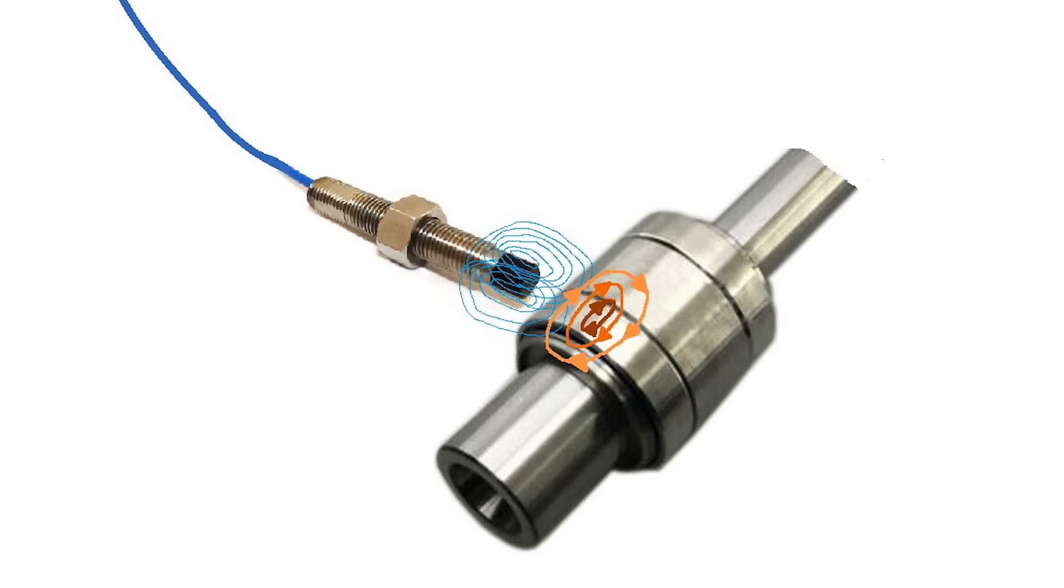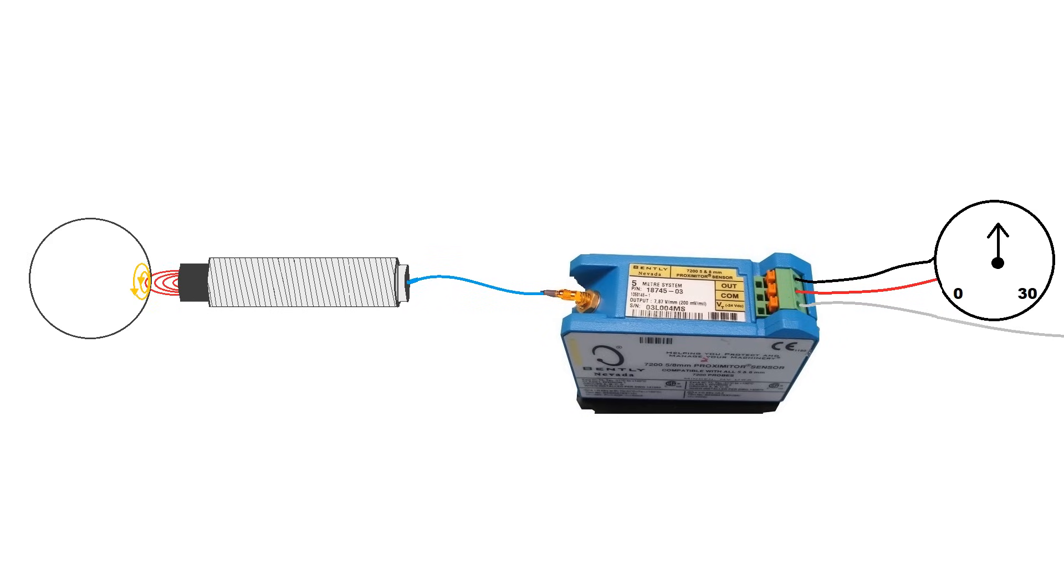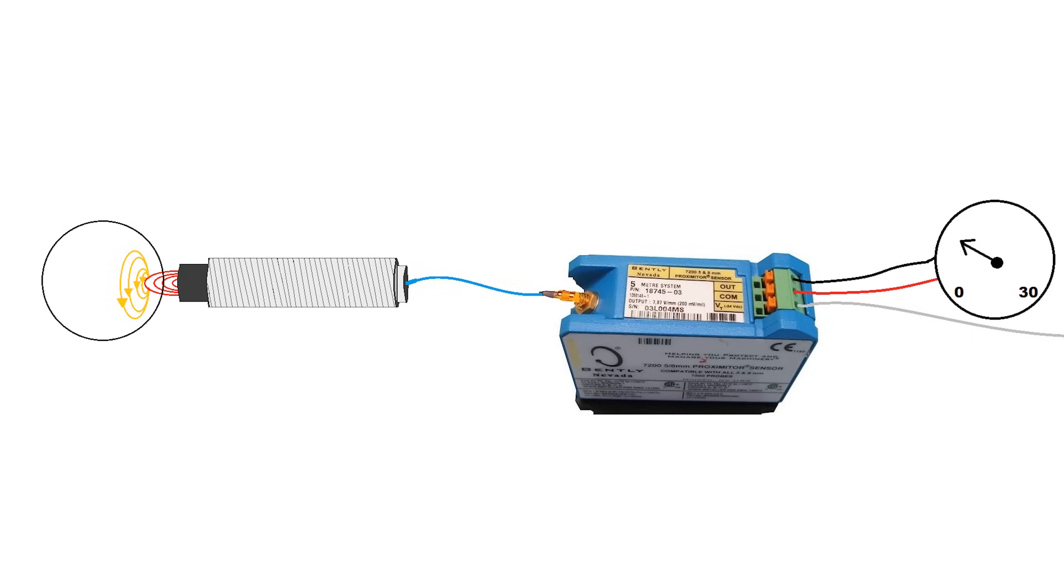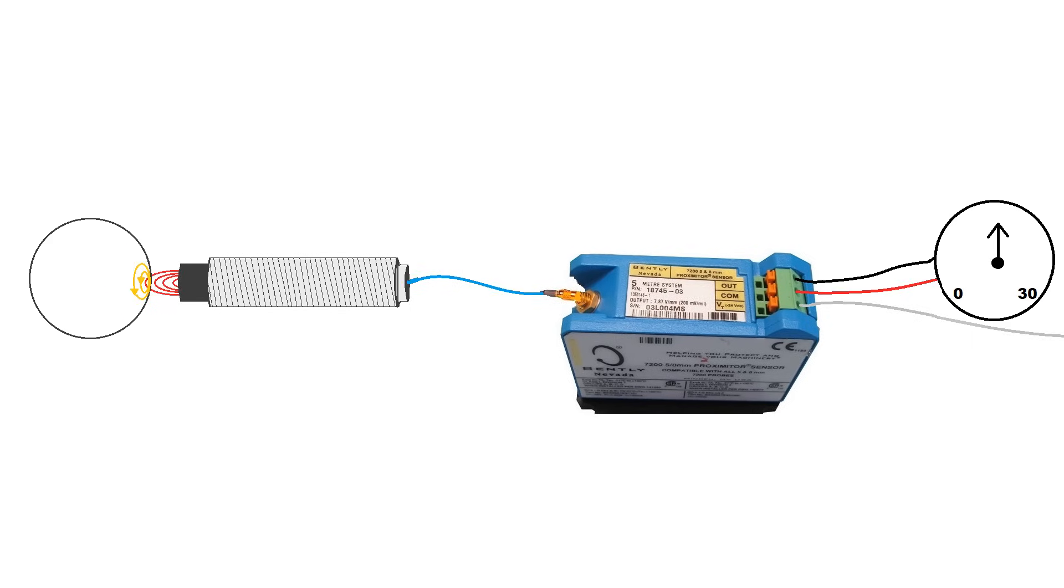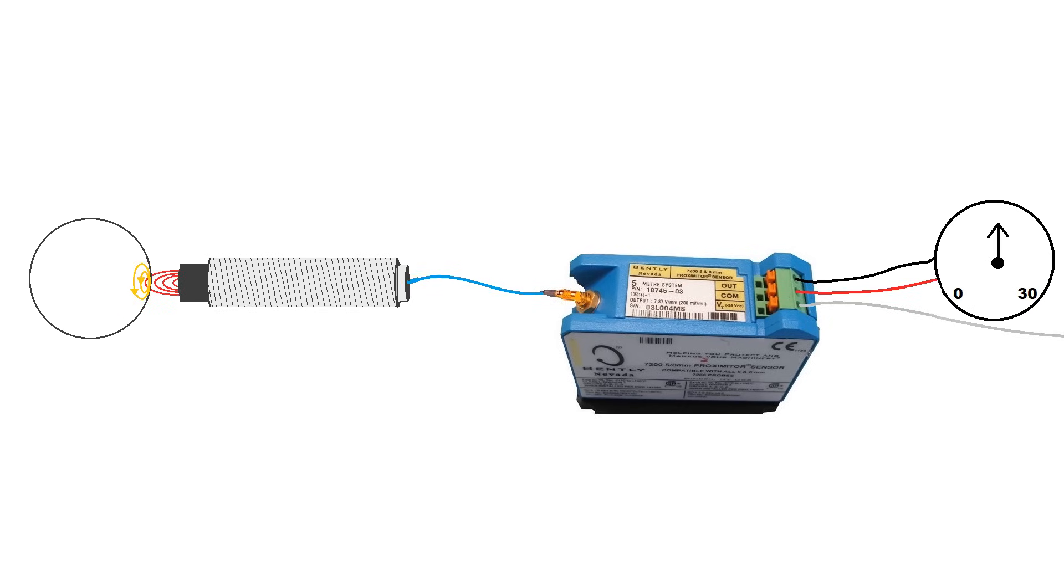The induction results in a loss of power. This loss of power is translated as a voltage change on the output terminals of the proximitor. The closer the metallic object is to the end of the probe, the more induction will occur and therefore the lower the output voltage of the proximitor. As the object moves away from the end of the probe, the output voltage will increase.